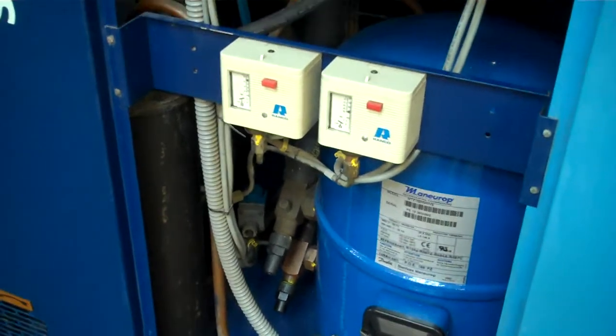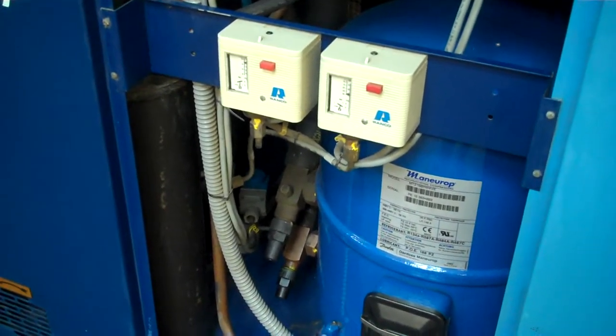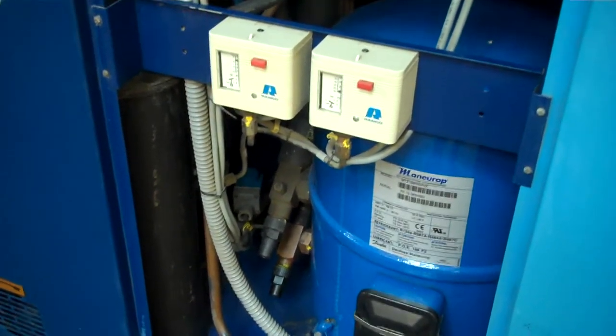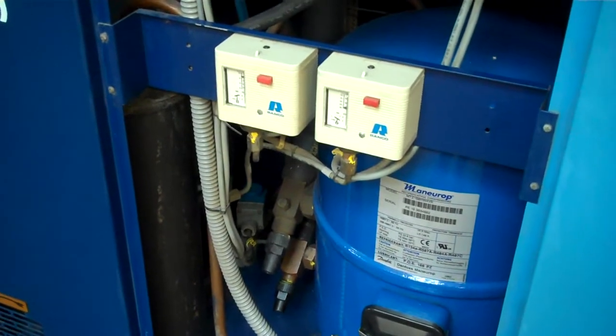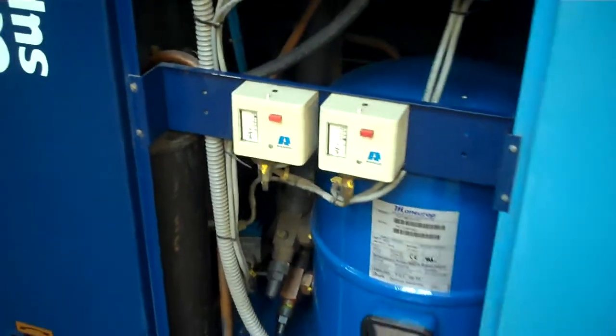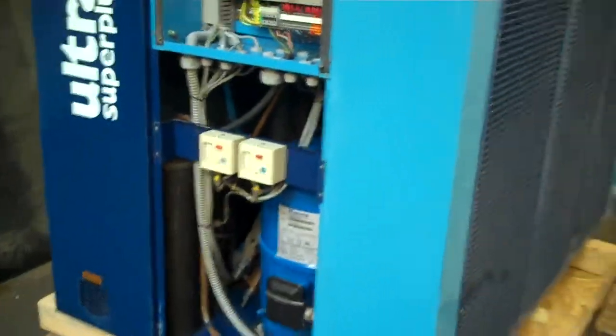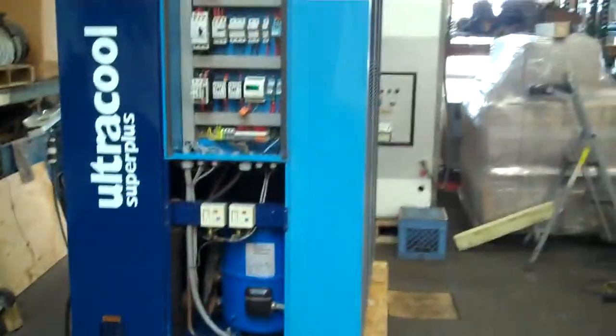Again, as most portable chillers are, this is set up as a closed loop style, meaning that same flow and output going out to your process, we're assuming it's going through an exchanger, a coil, or some type of jacket, because that same flow is what's coming back into our chiller.